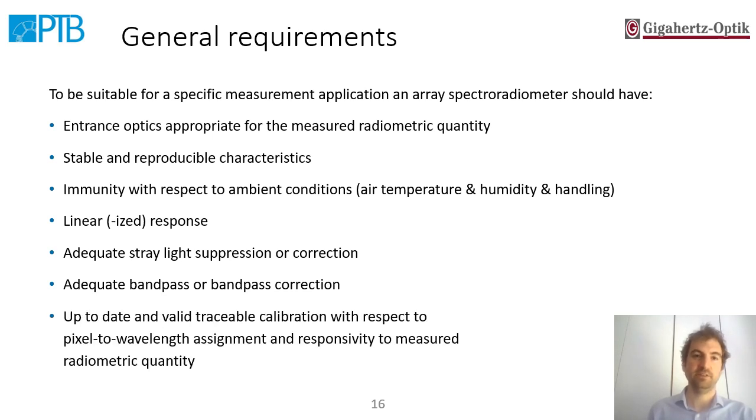Furthermore, you should think about bandpass or bandpass correction. And you need an up-to-date and valid calibration of your wavelengths and responsivity. So depending on your application, some of these requirements are more important or less important. But at least this is a list you can think about for your application.